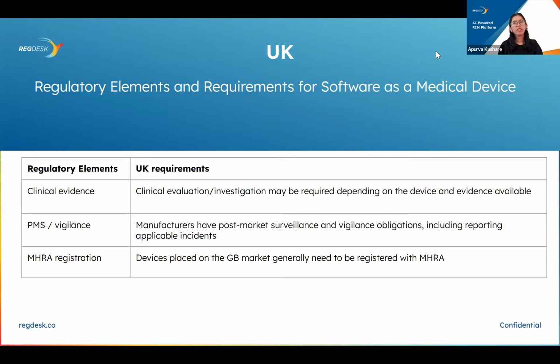So also in addition to this, it is crucial to revisit the processes and the intended purpose at key phases of the product development life cycle, which includes the post-market phase as well. So the new evidence and a greater understanding of product performance in the real world setting act as a feedback loop for many manufacturers, and there can be new information obtained so that the intended purpose can further be developed. So, also identifying gaps in evidence that restrict the expansion of the intended purpose elements should be addressed through planned activities such as the PMCF studies. So, that is another critical aspect.